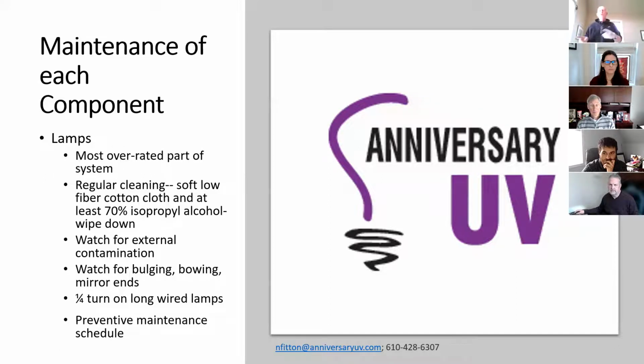All right, now the most overrated part of a UV system is the lamps themselves. As soon as something goes wrong, our first inclination is it's a bad lamp. It has to be a bad lamp. When I'm in my kitchen, I flip the light, it doesn't go on, it's a bad light bulb. In this case, try not to make that conclusion too quickly. In most cases, it's not going to be the lamp, it's going to be something else. So before you conclude it's a bad lamp, give me a call so we can talk it through.